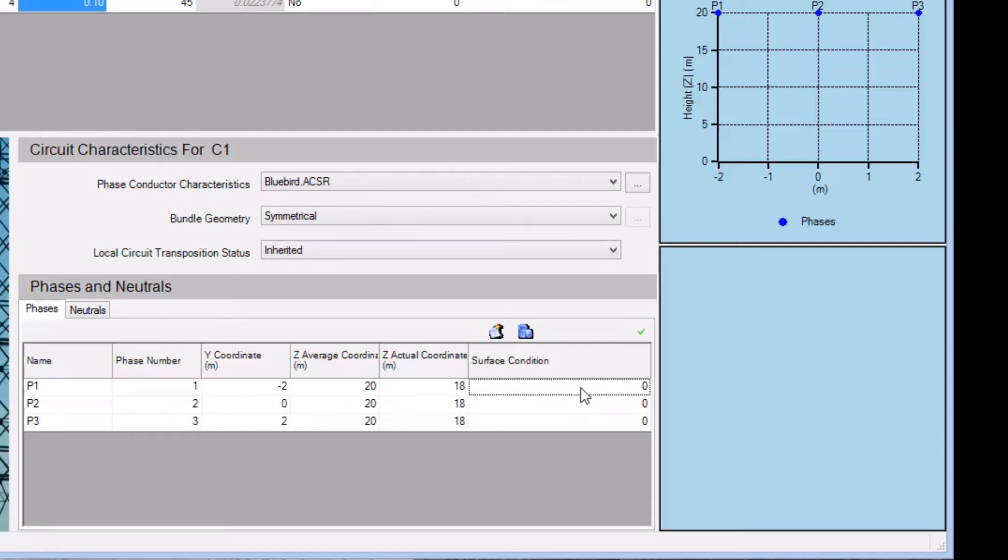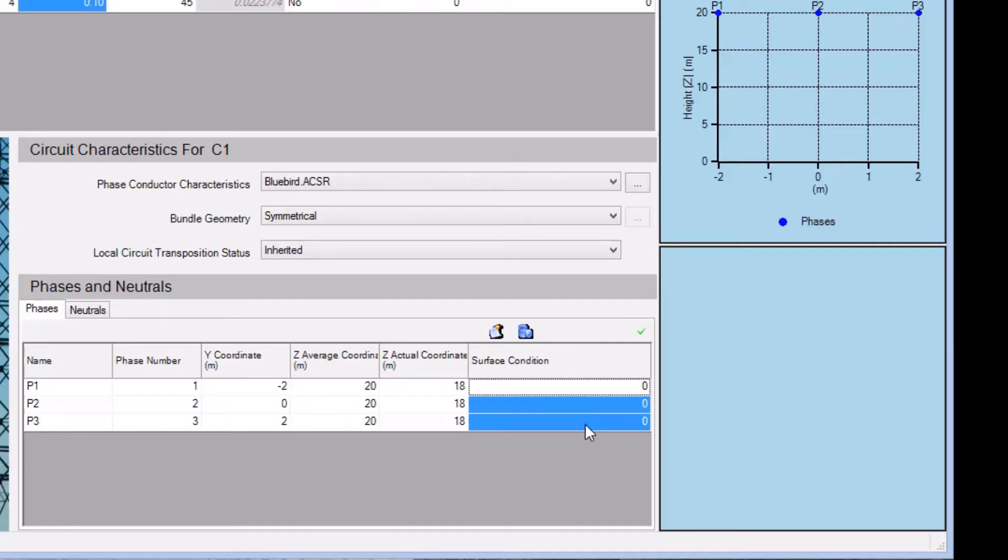Characteristics of a conductor are affected to a certain degree by a surface condition, and this is taken into account in this column. We would enter 0 for a brand new conductor and 1 for an old conductor. Typical conductor values vary from 0.3 to 0.4. We'll use 0.3 for our example.